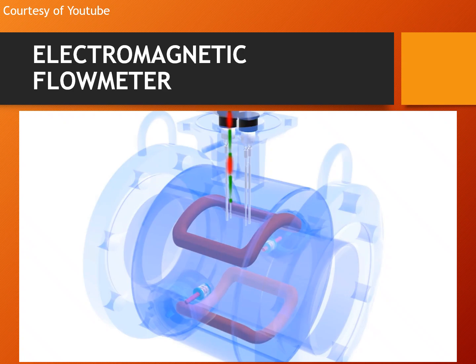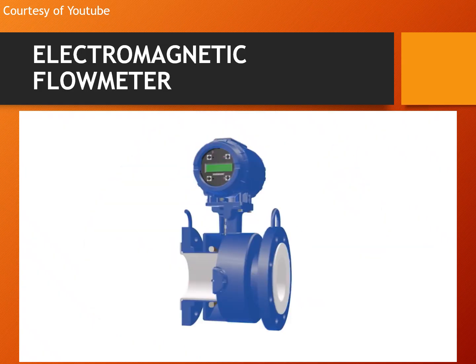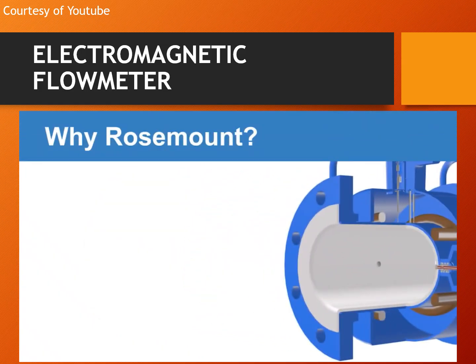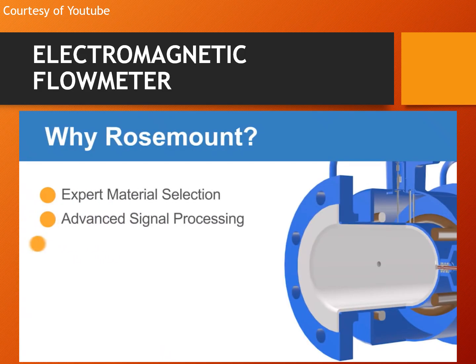Process noise occurs when particulates impacting the electrode interfere with the induced voltage measurement, generating a false reading. Rosemount has become a true expert regarding material compatibility for appropriate liner and electrode selection, and has advanced digital signal processing software to provide maximum measurement reliability for even the most challenging applications.